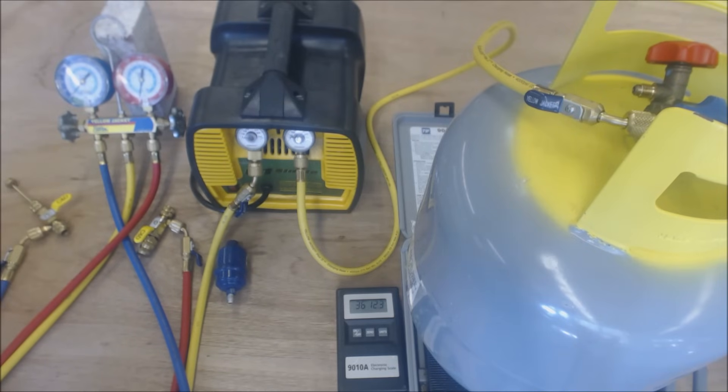I'll tell you that I was dealing with R-410A refrigerant, recovering refrigerant out of a system that had 13 pounds of refrigerant, and between zero and 10 inch Hg I had a pound and a quarter or so of refrigerant. So I would not advise pulling down to that level if you have a leak, because then you're just going to pull air right into the recovery tank. You don't want to do that.